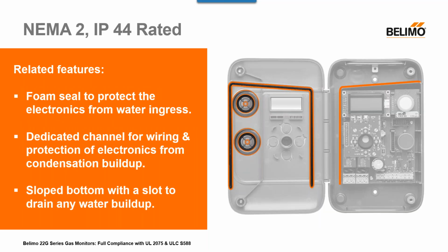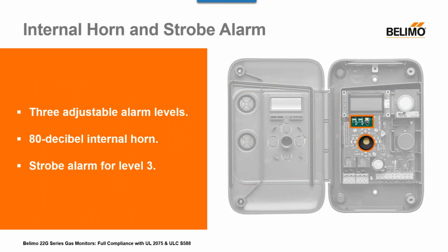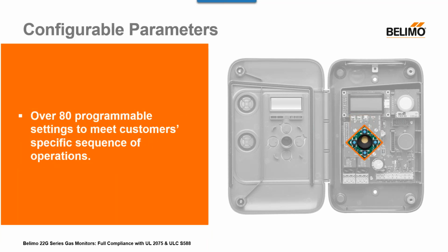Belimo gas monitors are housed in a sleek but robust NEMA 2 IP44 rated enclosure with a foam seal that protects the electronics and sensors from water ingress. They have a dedicated channel for wiring that also serves as an outlet from any condensation buildup and a specific condensation drainage system. We also offer splash-proof enclosures for more aggressive environmental applications. The monitors have 3 adjustable alarm levels that include an internal horn and strobe for alarm level 3 that is rated to 80 decibels. They have a 4-button keypad with over 80 programmable settings to meet your customer's specific sequence of operations, and also have password protection and optional security screws.